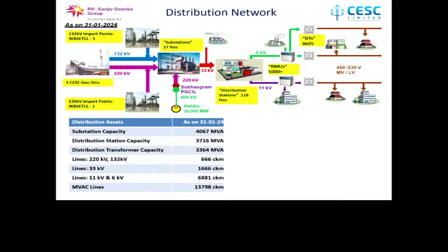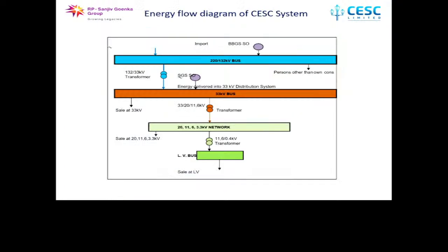These distribution stations have multiple, and in some cases single, transformers of 33 kV by 11 or 6 kV. There are 17 substations, where we have 220 kV or 132 kV transformers, and we have distribution transformers across this entire network area. As on date, the number of distribution transformers is a little more than 8,500, and we have RMUs also, at 33 kV and 6 and 11 kV.